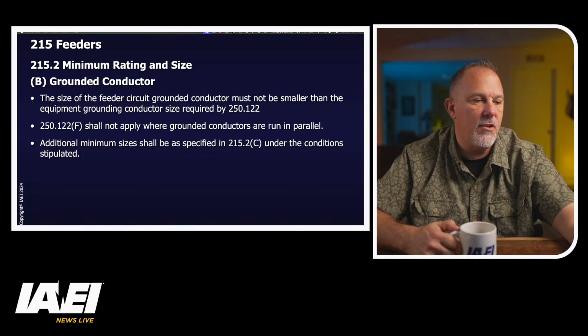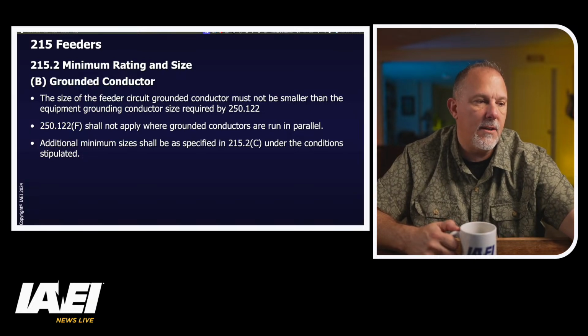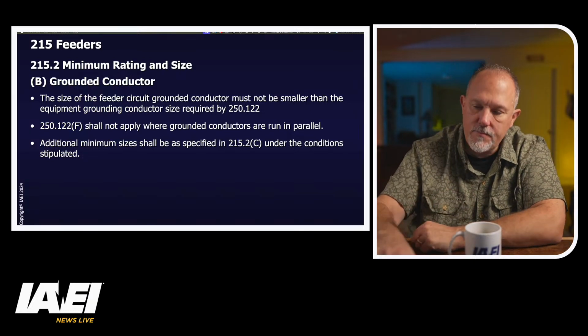All right, so let's take a look at 250.122(A). This is the general requirements. 250.122(A) tells us copper, aluminum, or copper-clad aluminum grounding conductors. That's grounding conductors. So it wants the grounded conductor to be no smaller than the equipment grounding conductor size. That's interesting. So I size the equipment grounding conductor, and then I make sure that my grounded conductor is the same size or larger.